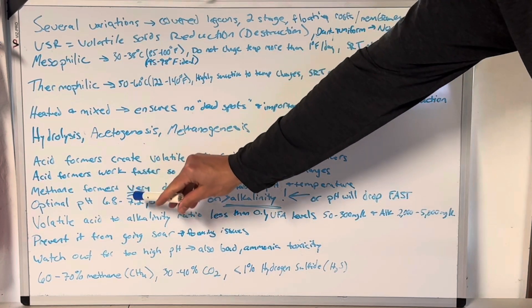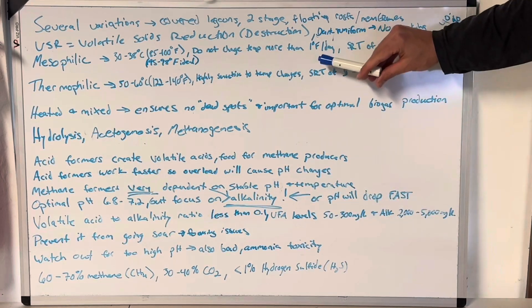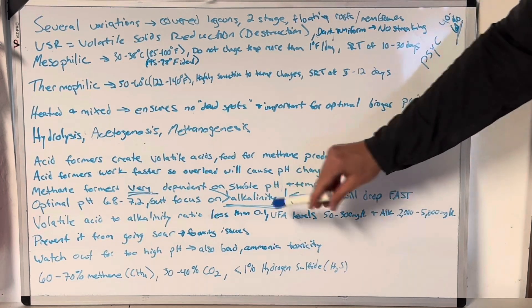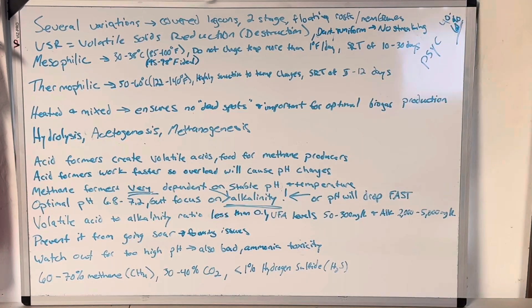Methane formers or producers are very dependent on stable pH and temperature. We already talked about temperature. How do we make sure that the pH is stable? Well, you've got an optimal pH range of 6.8 to 7.2. I'd really like to see it 7 to 7.2 personally. But you don't really focus on pH. That is not the process control you should be looking at. You focus on alkalinity.